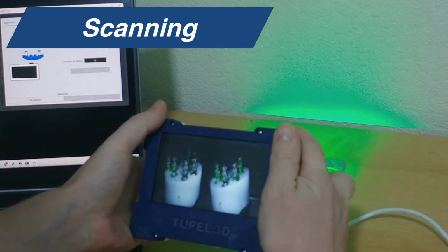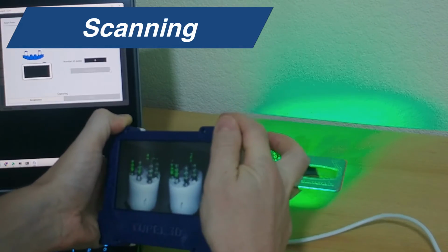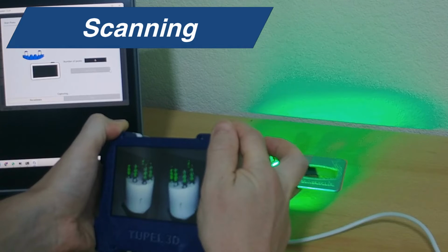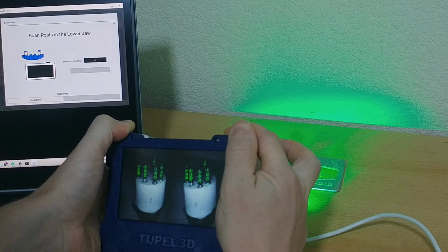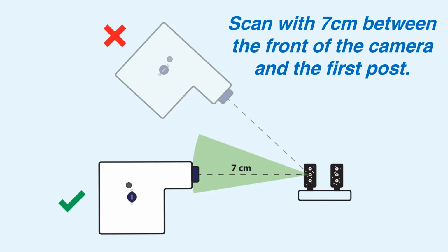If we take another look at scanning, the most important thing is to be at the right scanning distance. It's the same as for calibration. When you're at the right distance, the posts will be central in both images on the camera, and the dots on the posts will all be lit up green. It's a good idea to do a practice scan and measure out the ideal scanning distance so you can get a feel for the distance that you're aiming for.